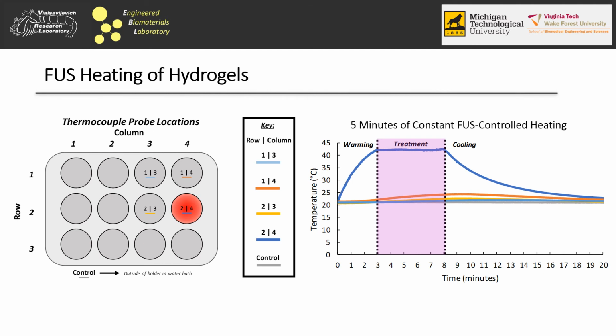With this setup, we inserted thermocouples into different wells of our sample holders and targeted this well by warming it for 3 minutes to a temperature of about 41 degrees Celsius and maintaining that temperature for 5 minutes, whereafter the targeted sample was allowed to cool down. Thermocouple probe results indicated tight spatial and temporal control of focused ultrasound treatment as indicated by the near instantaneous transition among warming, treatment, and cooling phases, as well as minimal heating of the surrounding wells in the sample holders.